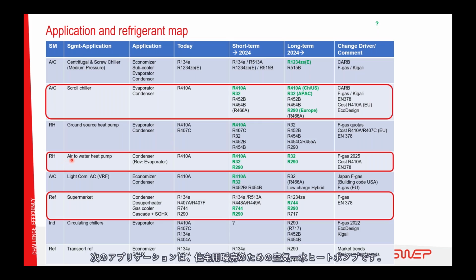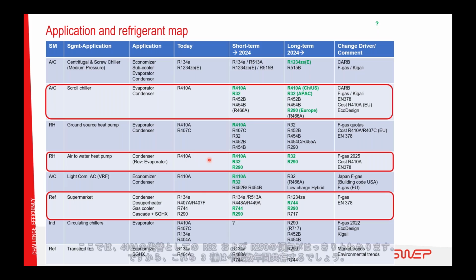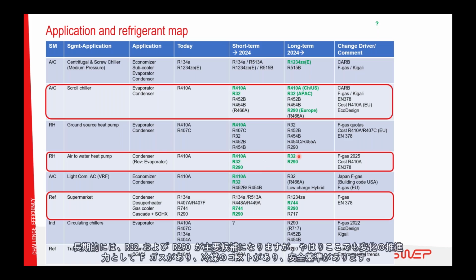Next application is air-to-water heat pump for residential heating. Typically, brazed plate heat exchanger is used as condenser. However, in reversible mode, it's being used as evaporator. R410A has been dominating until now. Here we see a clear trend towards R32 and R290 replacing R410A. So these three will exist together the coming years. Long term, we have R32 and R290 as the main candidates.